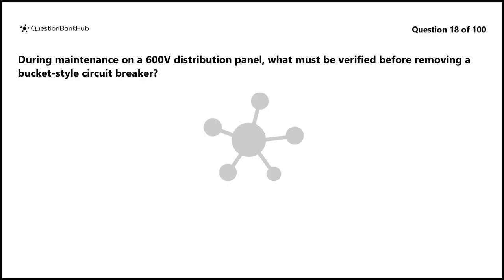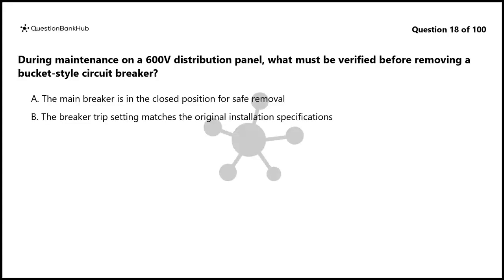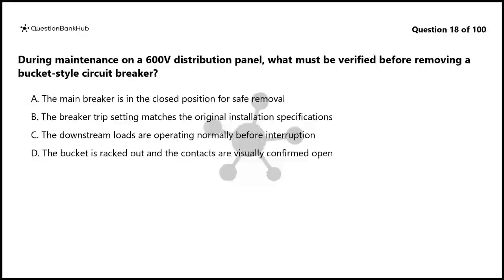Question 18. During maintenance on a 600 volt distribution panel, what must be verified before removing a bucket-style circuit breaker? A. The main breaker is in the closed position for safe removal. B. The breaker trip setting matches the original installation specifications. C. The downstream loads are operating normally before interruption. D. The bucket is racked out and the contacts are visually confirmed open.